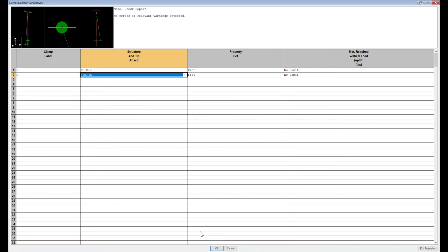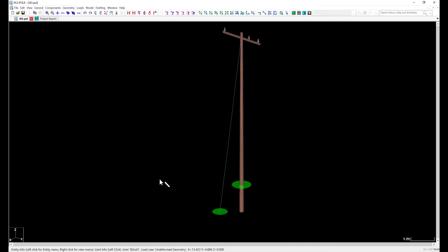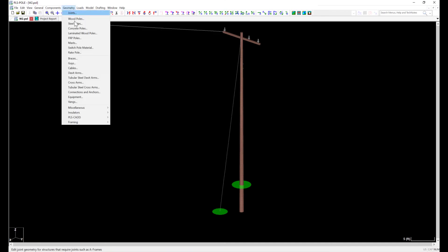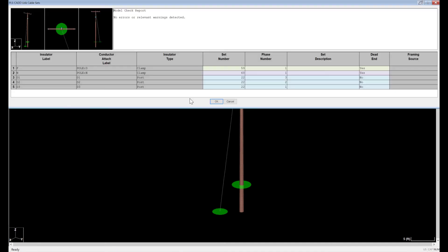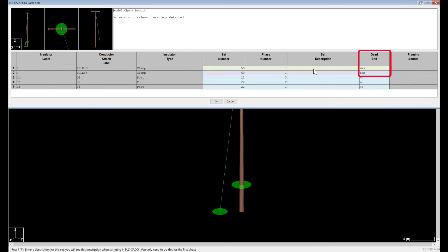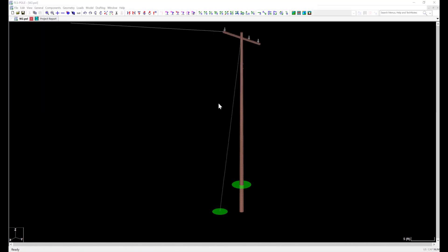Now I need to go to Geometry, PLS CAD, Insulator Link, to create a set to string to in PLS CAD. I'll go with something obvious, like set numbers of 59 and 60, with a phase of 1 for both. You'll also need to make sure that the clamps are dead ends. There will be no stringing through these clamps. The models with the conductor carrying poles are set up.